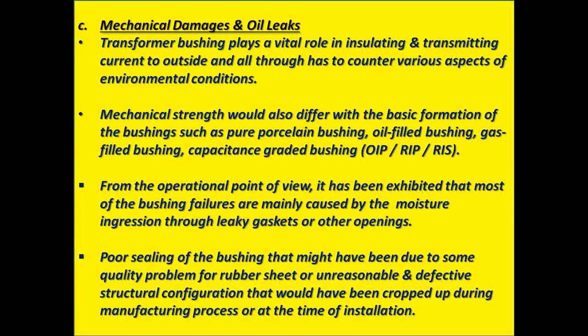From the operational point of view, it has been exhibited that most bushing failures are mainly caused by moisture ingression through leaky gaskets or other openings. Poor sealing of the bushing might have been due to some quality problem or manufacturing problem with the rubber sheet, or an unreasonable and defective structural configuration that cropped up during the manufacturing process or at the time of installation.